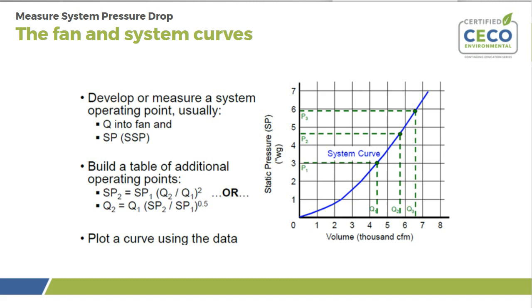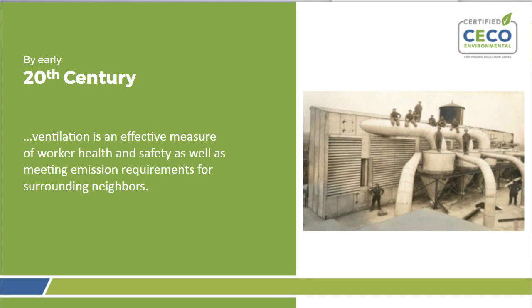This photograph is from the early 20th century, a Kirk & Blum installation at a woodworking plant. Back then, when you said dust collector, it was almost always a cyclone or centrifugal. It's coming up through the plant roof into the cyclone. In this case, we actually have what I think they referred to in those days as a doghouse, where any particulate that could bypass the collector, not spin out and drop out, is blown into this huge box that has louvered sections so the air comes out at a lower velocity. So hopefully any carryover material falls out within that box and not to the atmosphere.